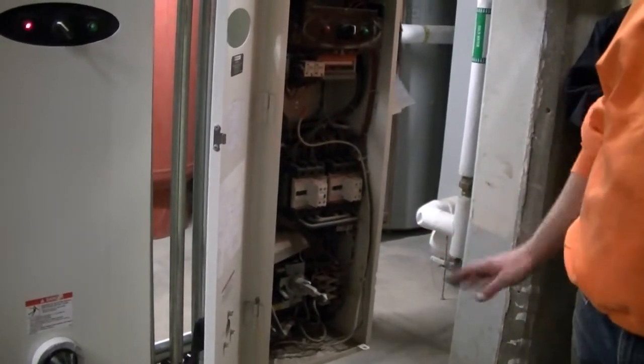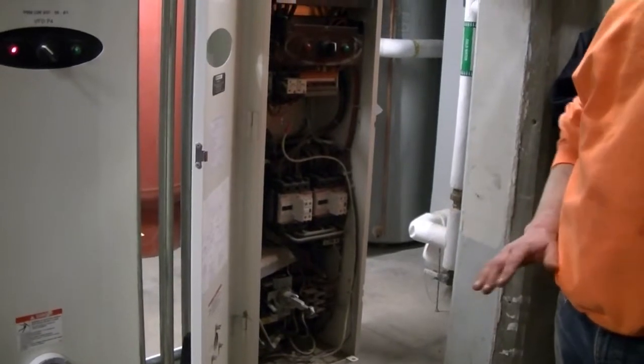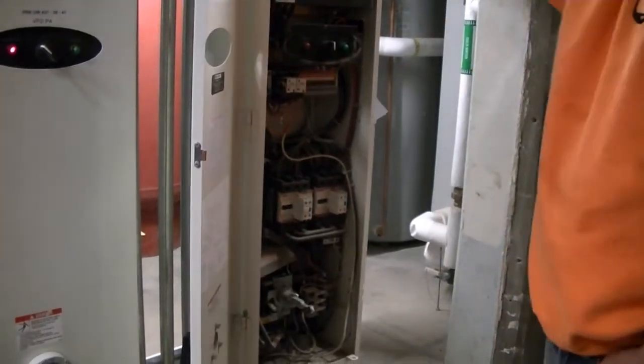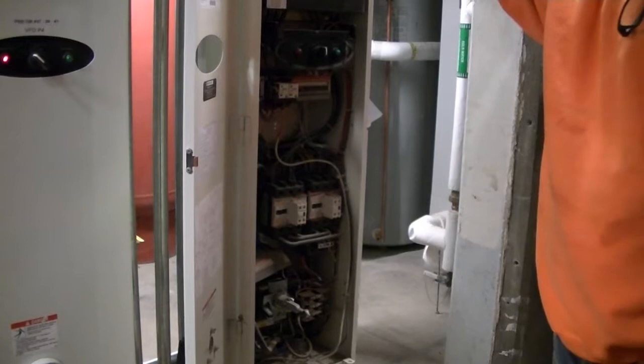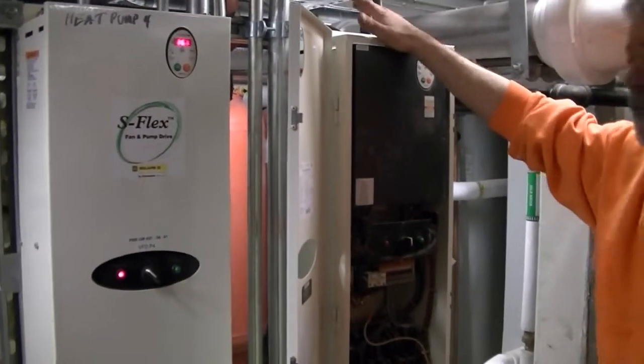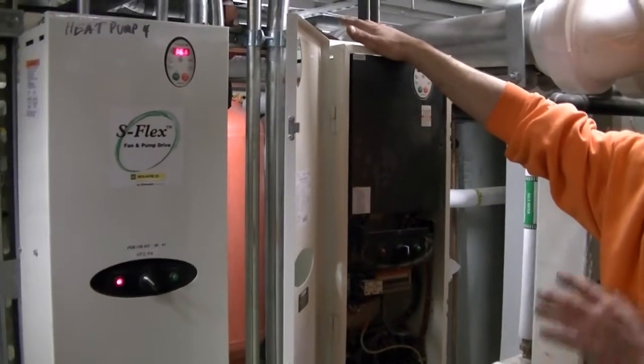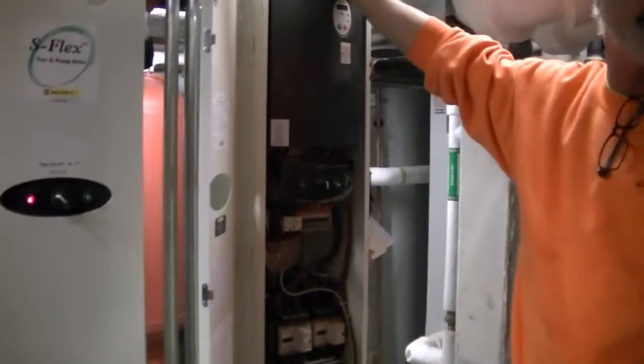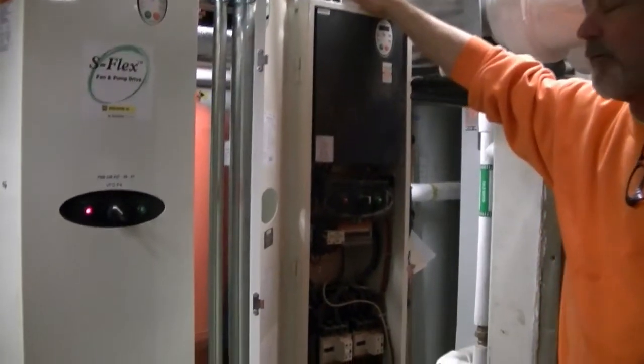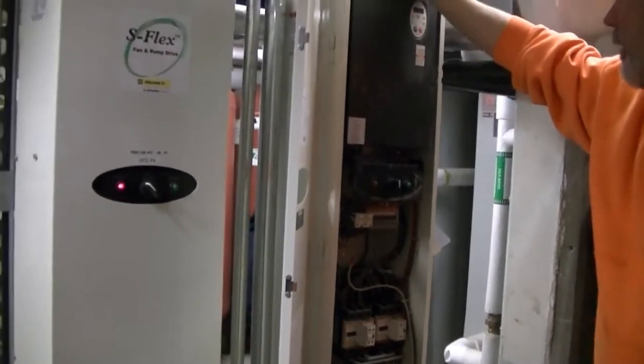You can blow it out with compressed air while it's not running. This is a mechanical space. It does have a ventilation fan located in the top of it. For no reason should you ever store anything on top of these drives, in front of them, or next to them. They do not operate well when they get hot. They have to be in a well-ventilated area.